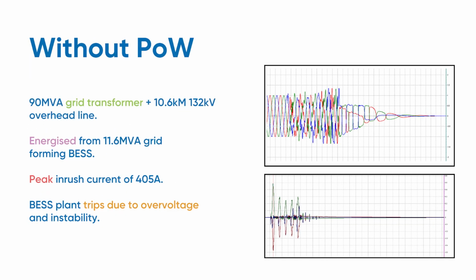So this was the first test that we did, and this was without point-on-wave. We just used the battery energy storage system to energize a 90 MVA grid transformer. It was a 33 kV to 132 kV, and 10.6 kilometers of 132 kV overhead line. So it energized. You see the initial inrush current.